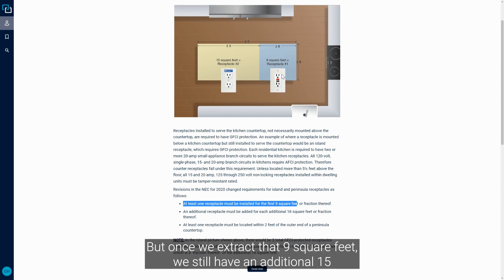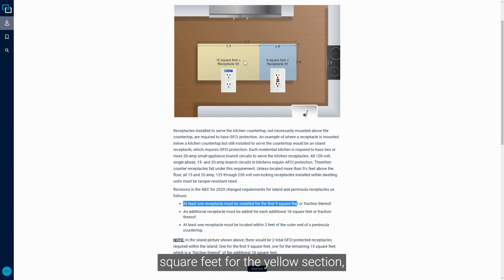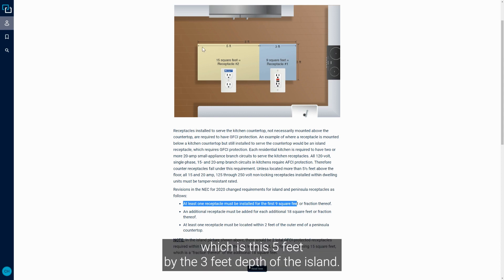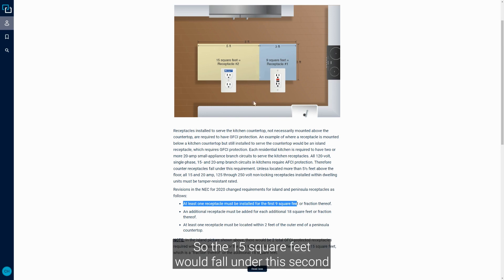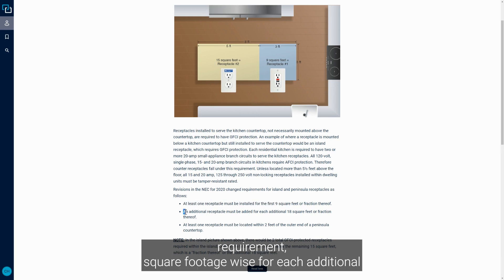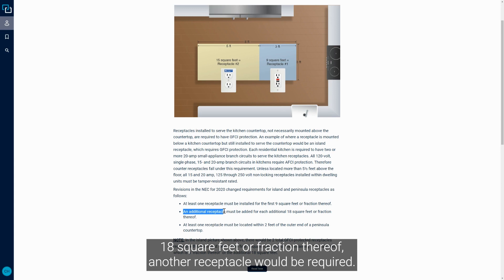But once we extract that nine square feet, we still have an additional 15 square feet for the yellow section, which is this five feet by the three feet depth of the island. So the 15 square feet would fall into this second requirement square footage-wise for each additional 18 square feet or fraction thereof - another receptacle would be required.